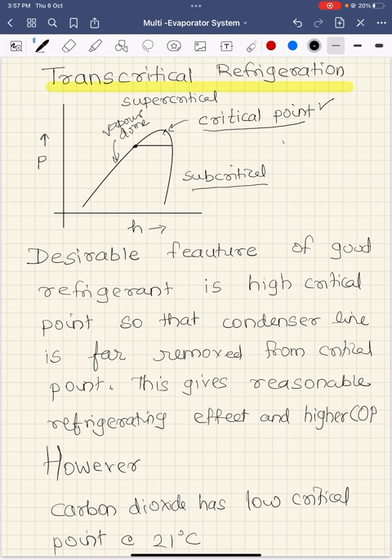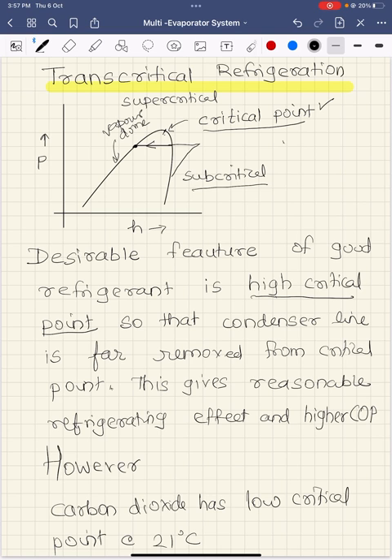A high critical point is a desirable feature. If you have a high critical point, when you are designing a condenser — suppose the condensation line is here — the condensation line is far separated from the critical point, and because of that the refrigerating effect you get is good enough. The cycle I am drawing here is the subcritical cycle. It is called a subcritical cycle because the refrigerant is condensing below the critical point — the entire vapor compression refrigeration cycle is operating in the region below the critical point.